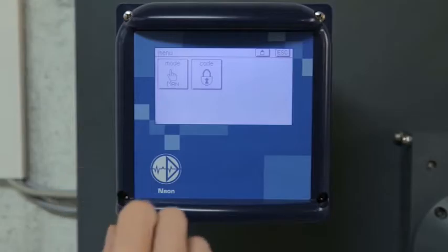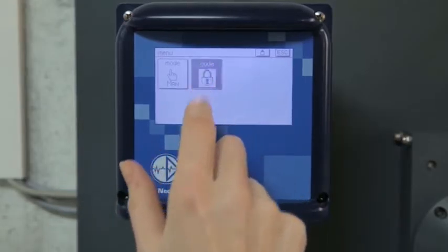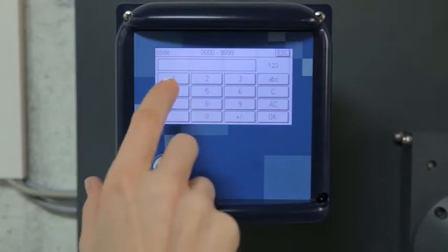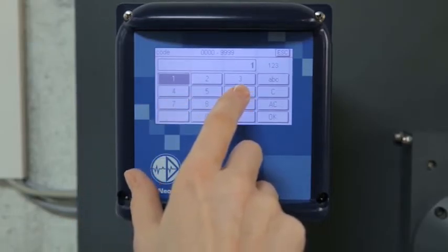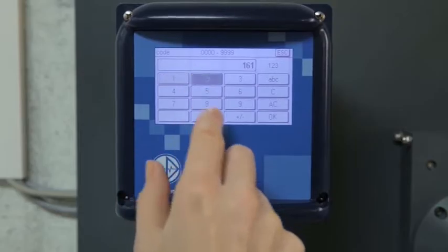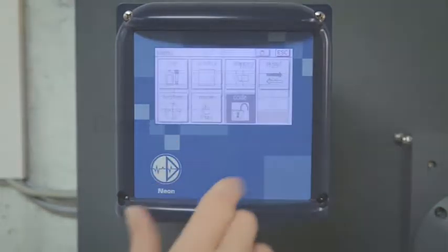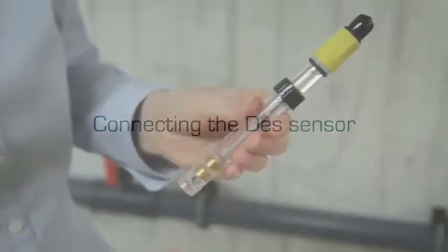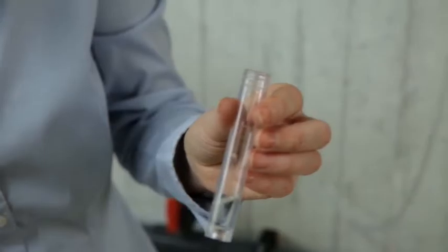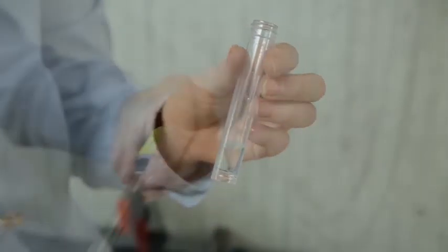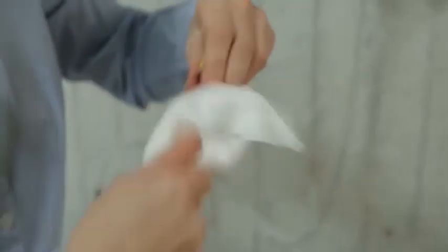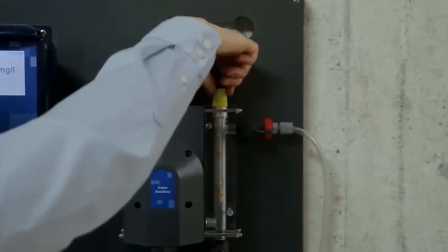No valid access code has been set at delivery. Use access code 1612 to access all parameters and settings. The sensor is delivered in a transport protection with highly concentrated saline solution. Remove the transport protection from the sensor and install it. Before you connect the cable to the sensor, check that the correct measuring parameters are set in the menu. Now connect cables and sensors.